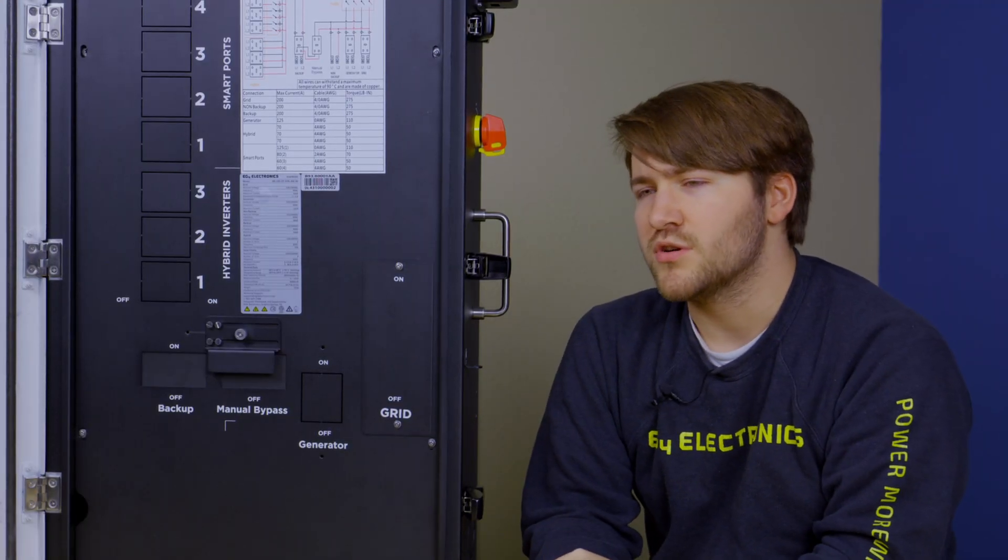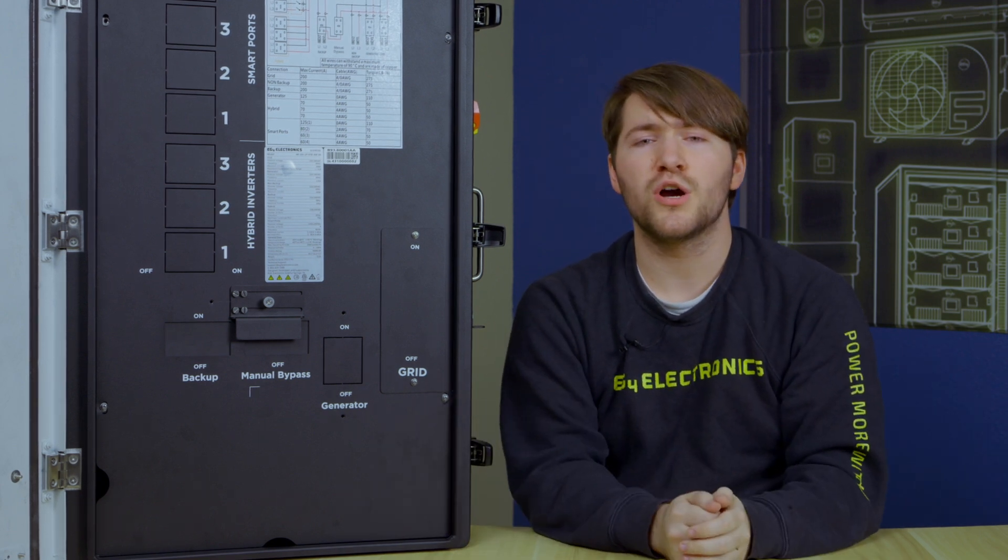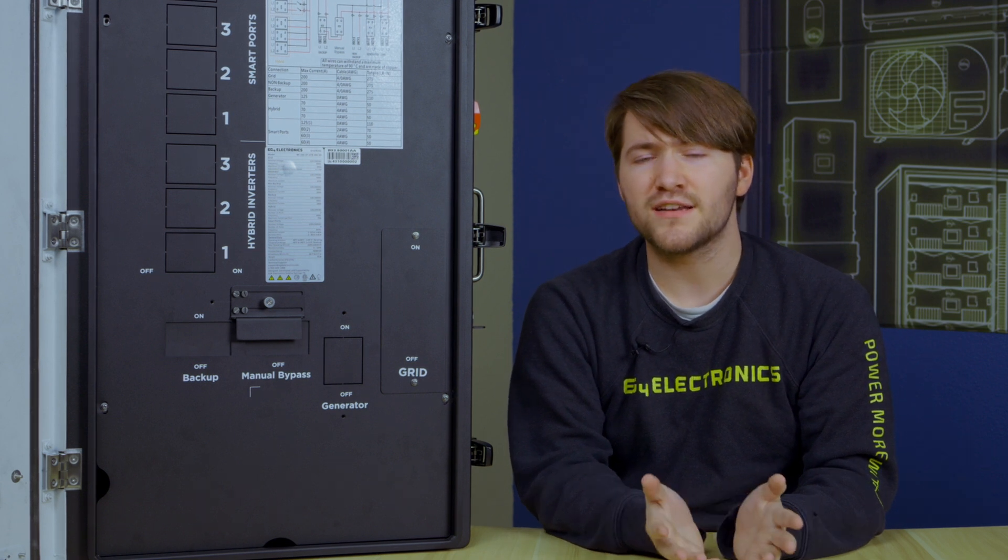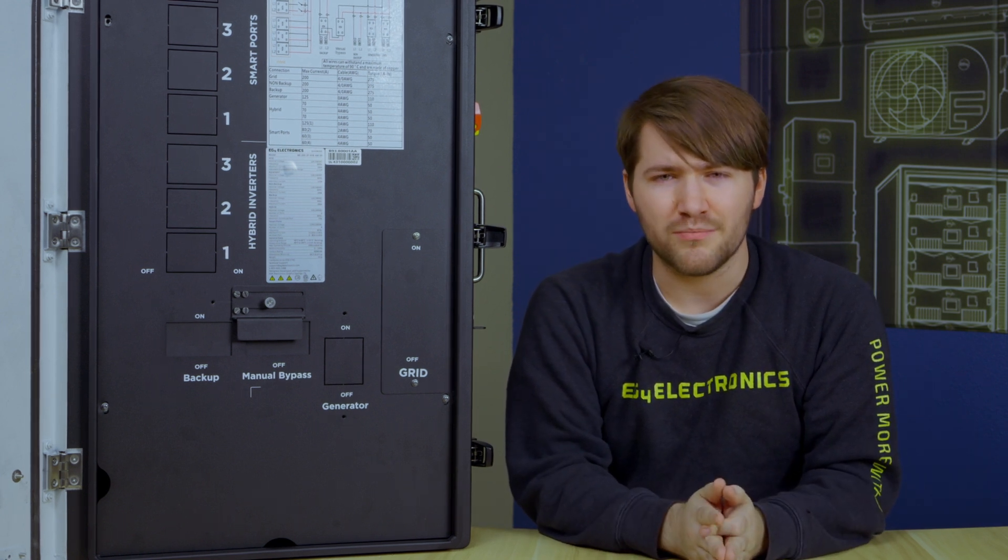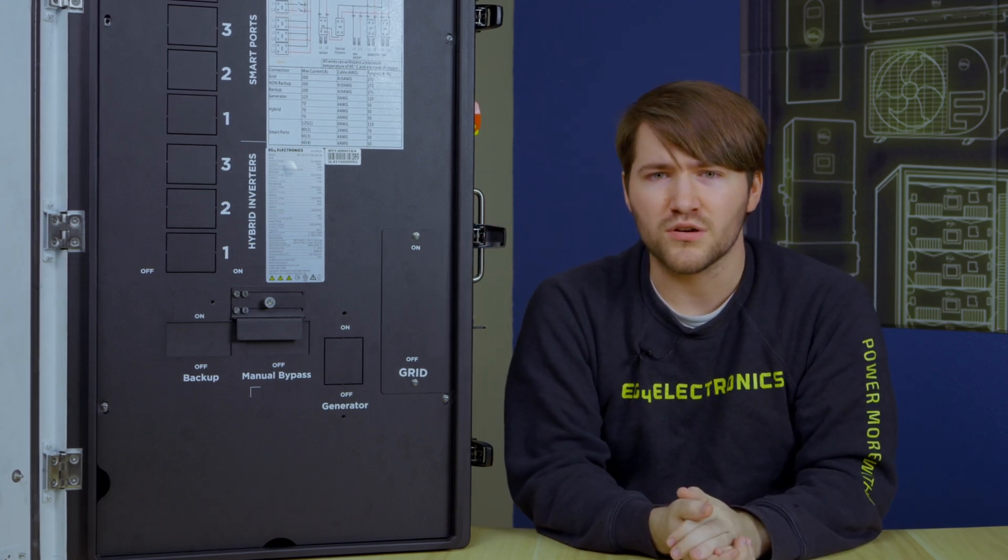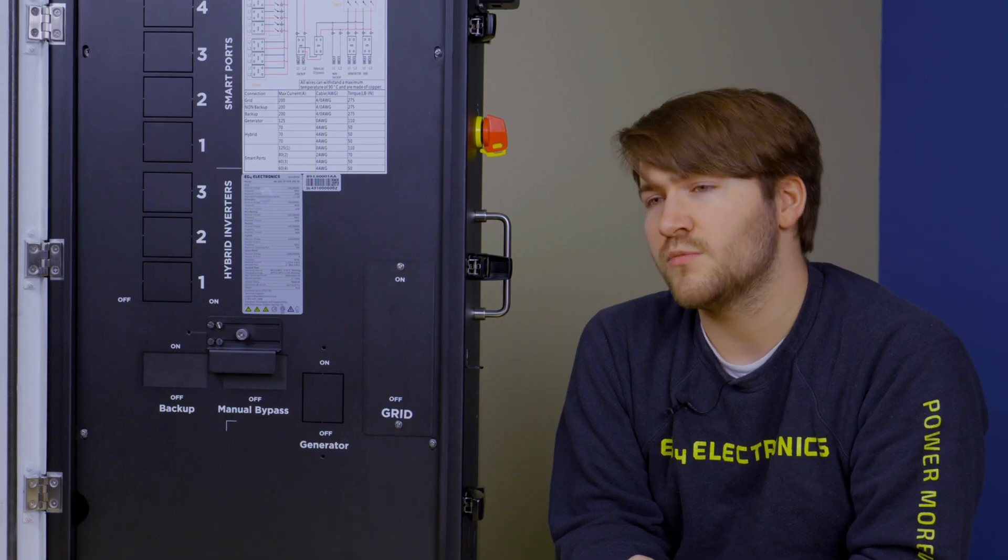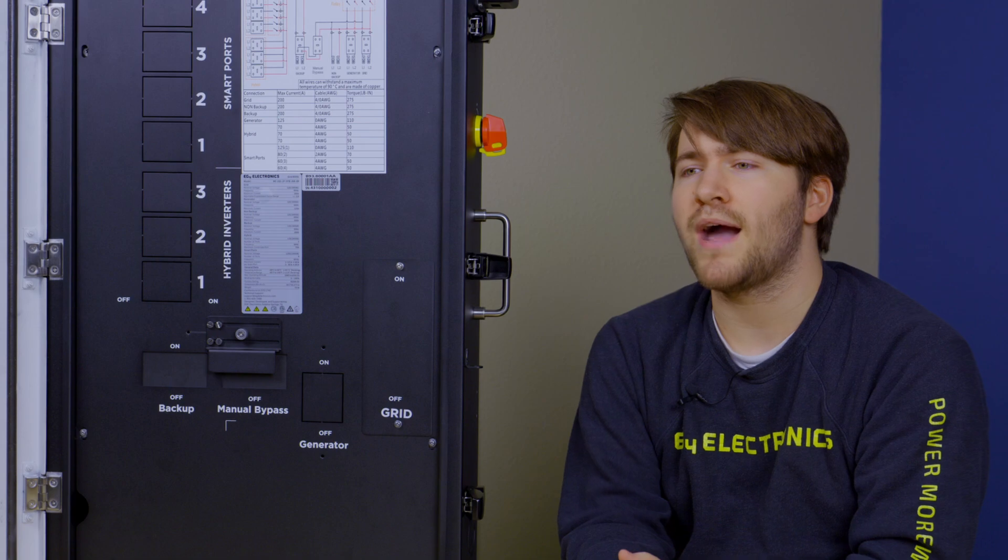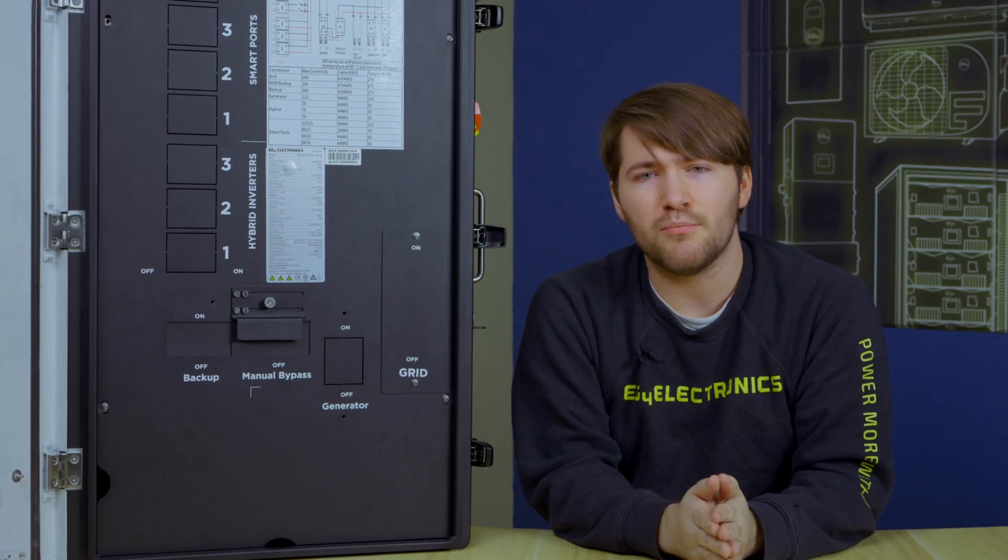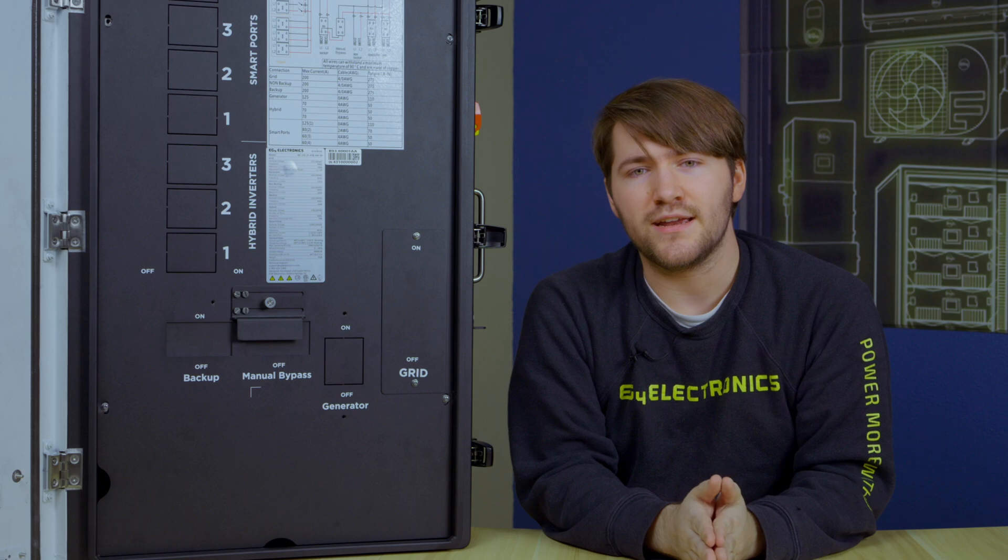And skipping the hybrid inverter ports for a moment, let's talk about the backup and the non-backup terminals under here. They're both rated for 200 amps, which is only possible through the power of PCS. And effectively, what you can do with that system is, say you have a load that you really don't want to run without grid power or something along those lines. You don't want to take up a smart port with that. So you can use that non-backup load for something that simply runs when the grid does and doesn't when the grid's not there. And then your backed up loads terminal is going to be what is constantly powered with everything possible hooked into the grid boss, be it AC coupled power, be it the hybrid inverters, generator if you have it, and then the grid that you have tied in here.